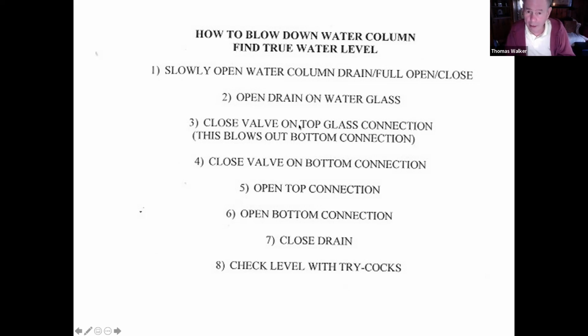So again, try to familiarize yourself with this procedure. The water column, all you have to do is open the drain valve fully wide and close it. That's because it's got fairly large connections to it. They're not likely to get plugged. The gauge glass, on the other hand, has needle type valves that are prone to getting plugged with sludge and sediment. The gauge glass, you have to blow out the top and the bottom valves independently of one another to make sure that neither one is plugged. And that's what this procedure comprehends. Any questions about water columns or gauge glasses?